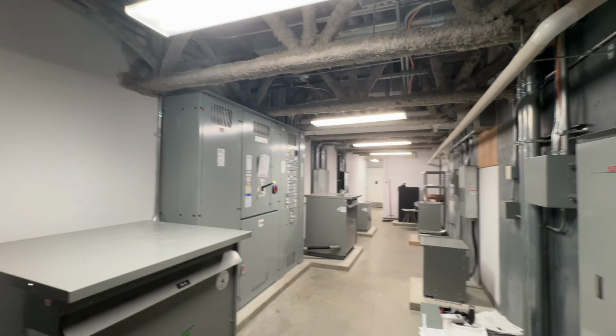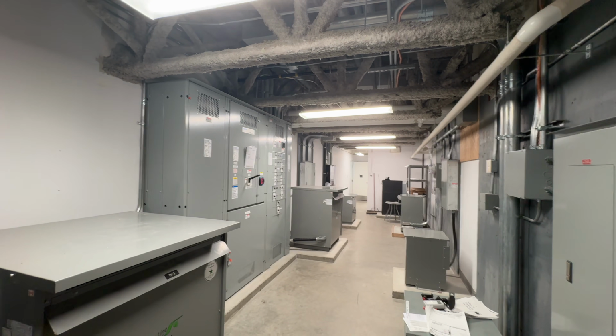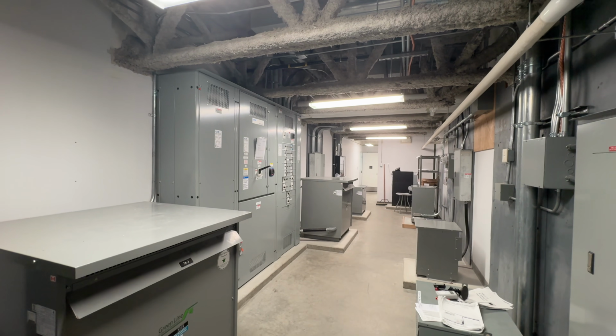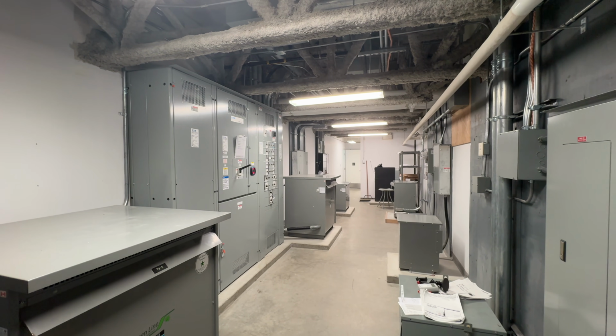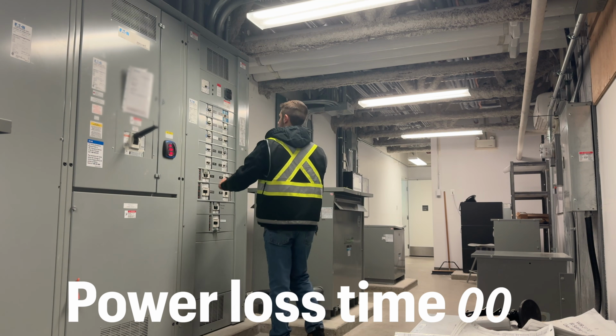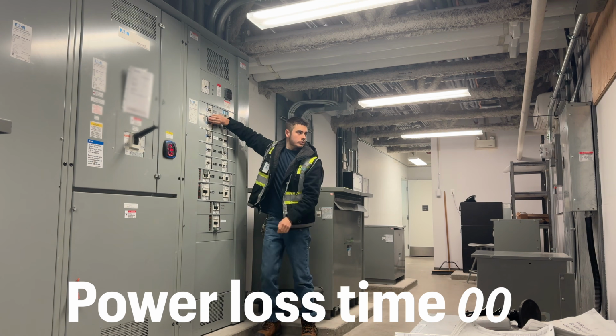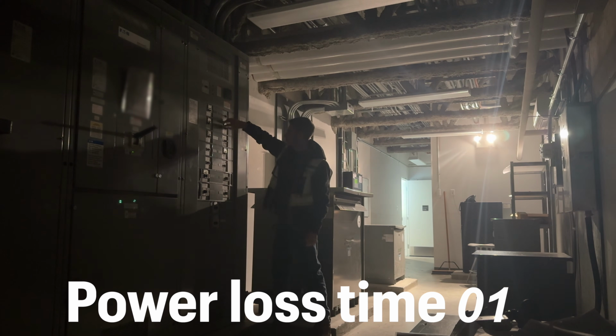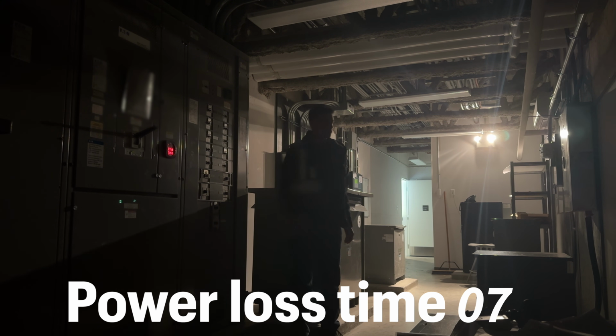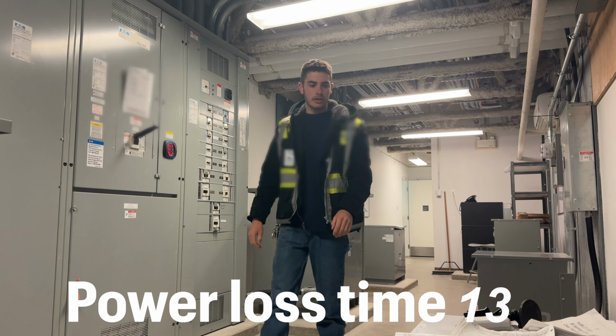All right, that's enough talk. Let's turn these breakers off. I'll start with the emergency one, as that does the lighting, so I can get a realistic timing on how long this system will take to start, and then I will hit the non-emergency power. Let's get it. And we are now running on generator power.